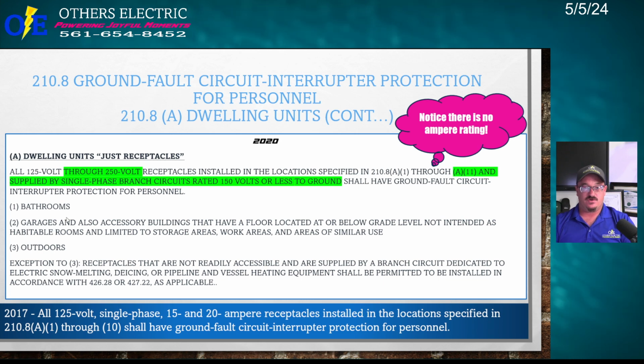Okay, so in the bathroom, if you have a receptacle that's 120 or 240 volt, it now has to be GFI protected. In the garages, any garage receptacle now has to be GFI, 120 or 250. If you've got a receptacle for a car charger, GFI protected. A receptacle for a dryer, GFI protected. A receptacle for anything else, GFI protected.